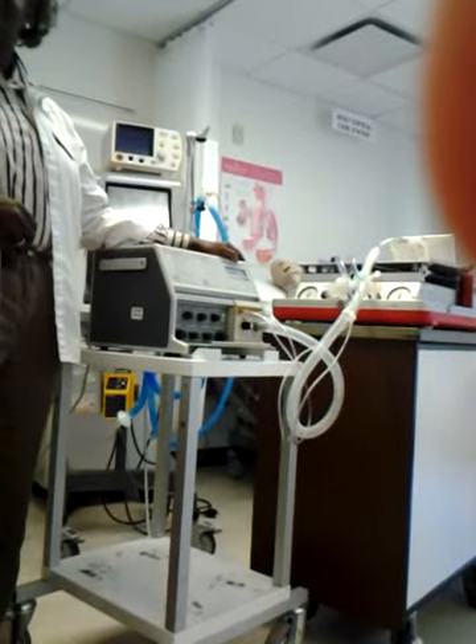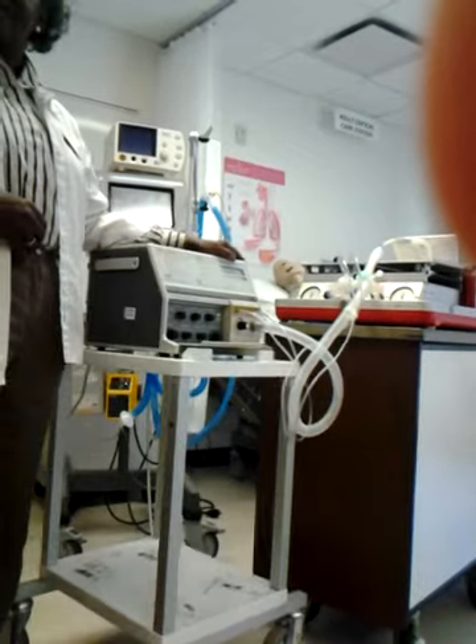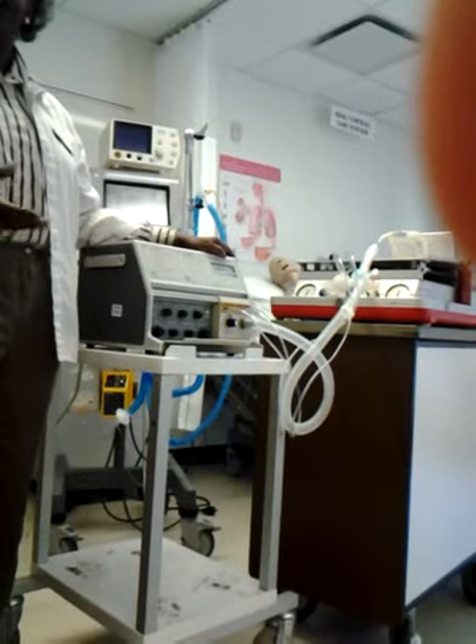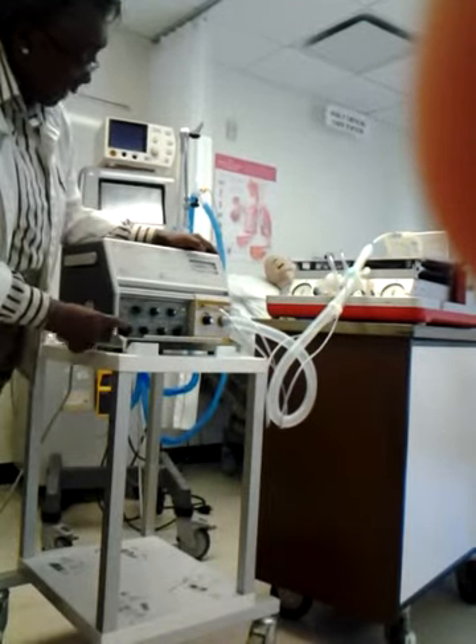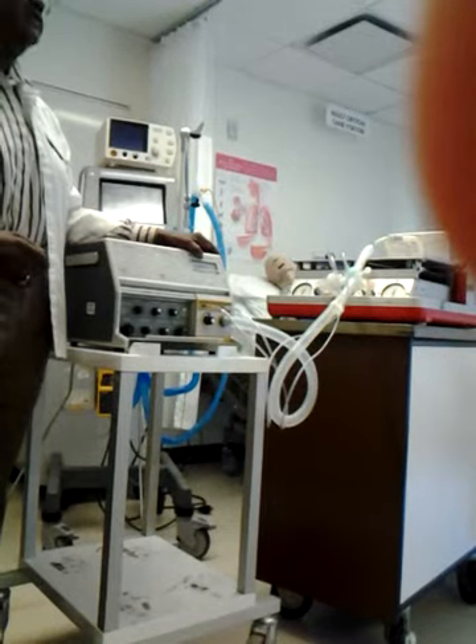Because it's just that. Yeah. So you can't actually check the delivered tidal volume. There's nothing that's reading it. There's no respirometer or anything. You'd have to put a respirometer in line. Just like when we did IPPB, you had to put a respirometer in line. Yep. Now you set your tidal volume, so you don't know if it's accurate. You can read your pressure, but you can't read your volume.